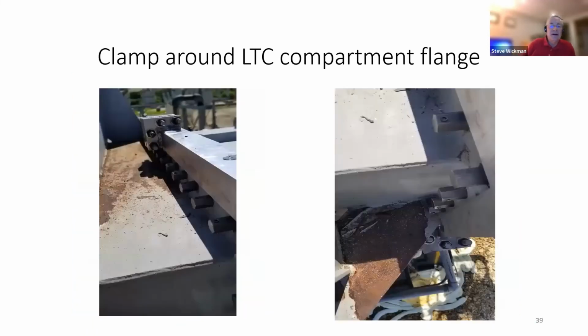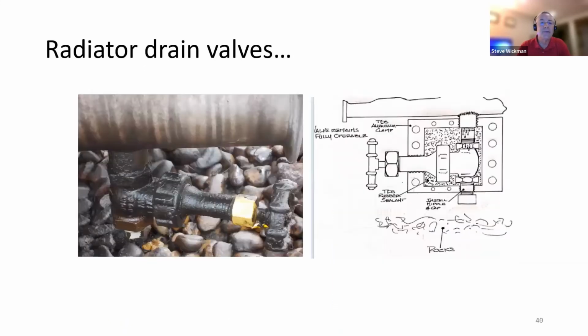In addition to the clamp, once you put the clamp on that flange, the oil is going to migrate to the holes where the nuts and bolts go together to hold those components in place. We will replace the nuts on the back side of the bolt hardware with a hollowed out sealant type nut that you can pump the sealant compound into also. Like I say, the oil is going to start to migrate to other places. This is also a very common fix used on SF6 repairs too.